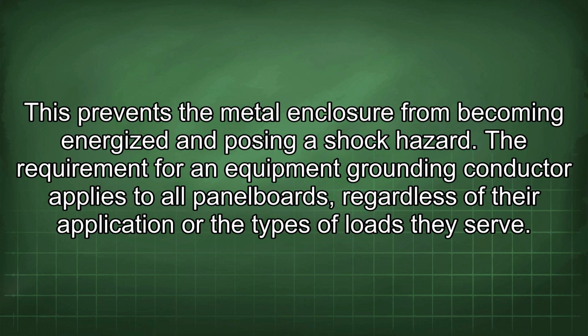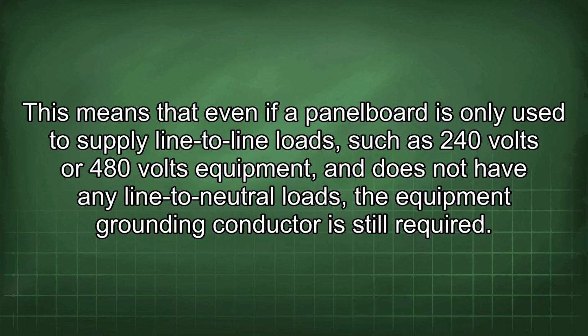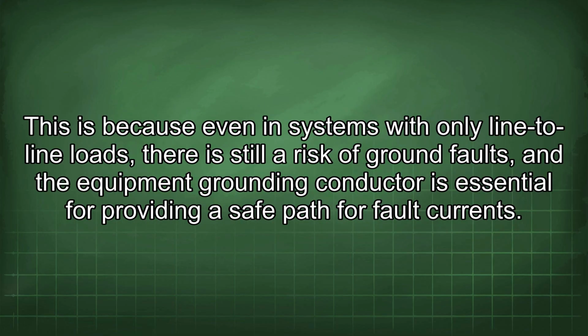The requirement for an equipment grounding conductor applies to all panelboards, regardless of their application or the types of loads they serve. This means that even if a panelboard is only used to supply line-to-line loads such as 240 volts or 480 volts equipment, and does not have any line-to-neutral loads, the equipment grounding conductor is still required. This is because even in systems with only line-to-line loads, there is still a risk of ground faults, and the equipment grounding conductor is essential for providing a safe path for fault currents.